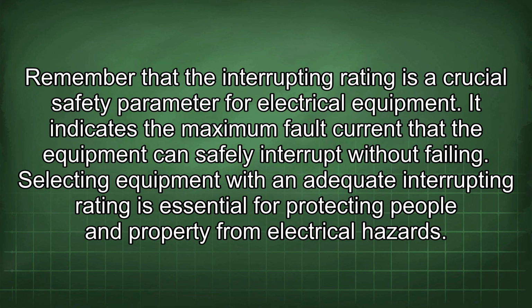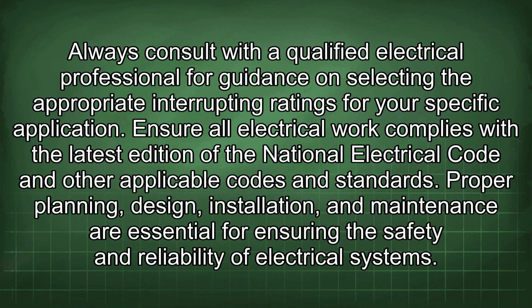Remember that the interrupting rating is a crucial safety parameter for electrical equipment. It indicates the maximum fault current that the equipment can safely interrupt without failing. Selecting equipment with an adequate interrupting rating is essential for protecting people and property from electrical hazards. Always consult with a qualified electrical professional for guidance on selecting the appropriate interrupting ratings for your specific application.